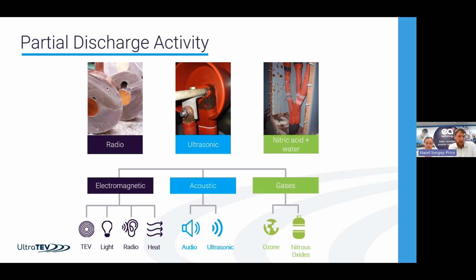Where that's occurring inside the insulation, that isn't an easy thing we're going to be able to access - we're not going to be able to see that pressure wave. But on the surface of the insulation, as in the middle picture there, this is actually a really good way of picking up early activity, hearing that crackling and sparking.